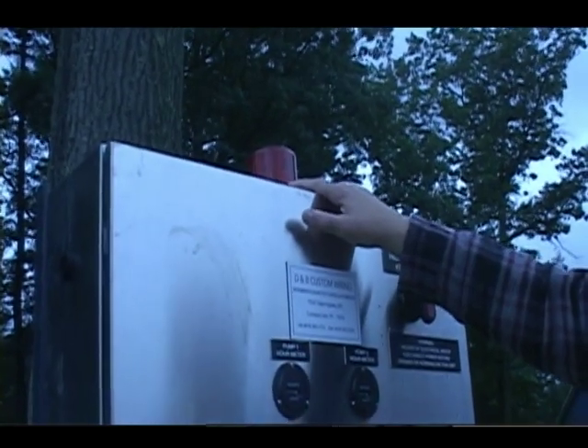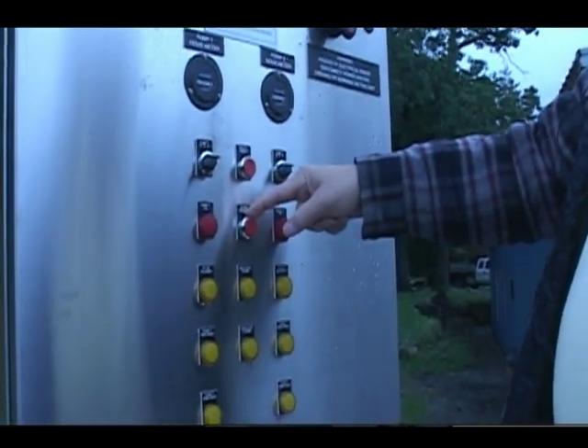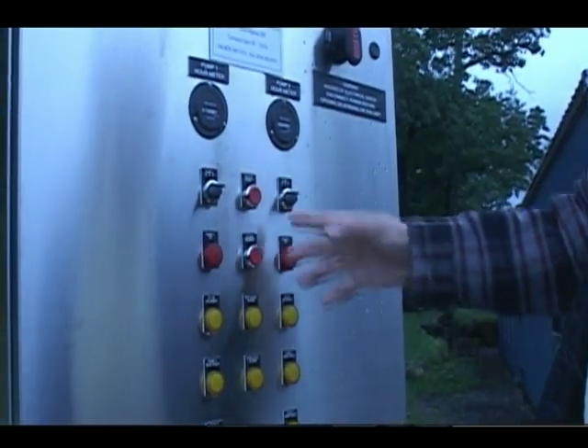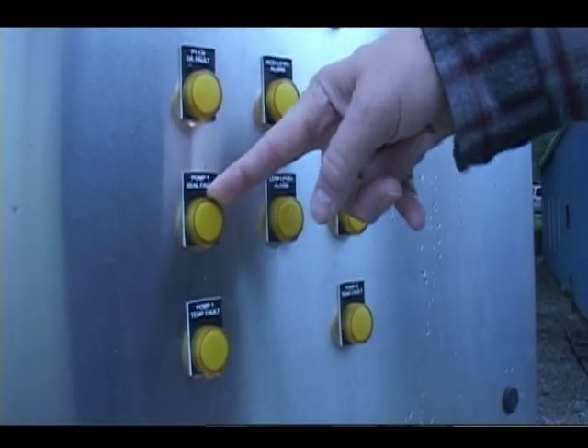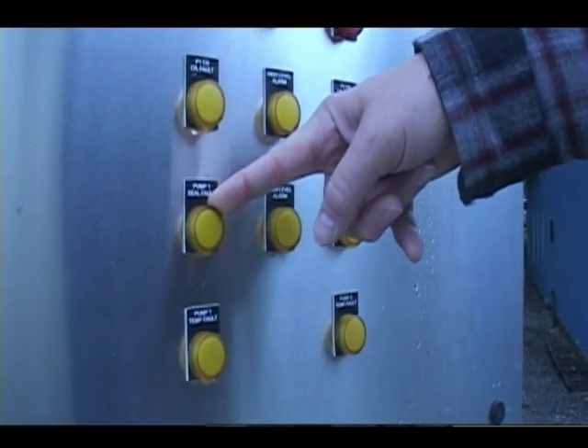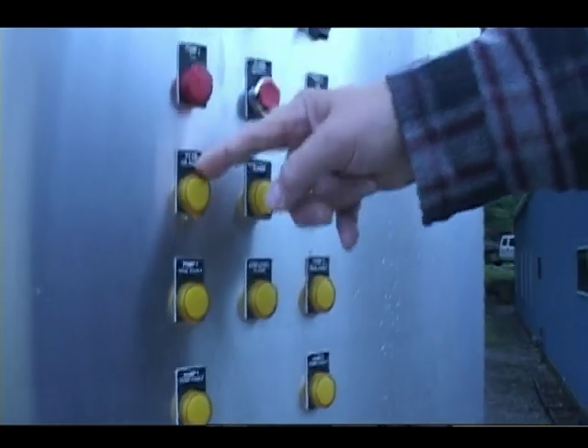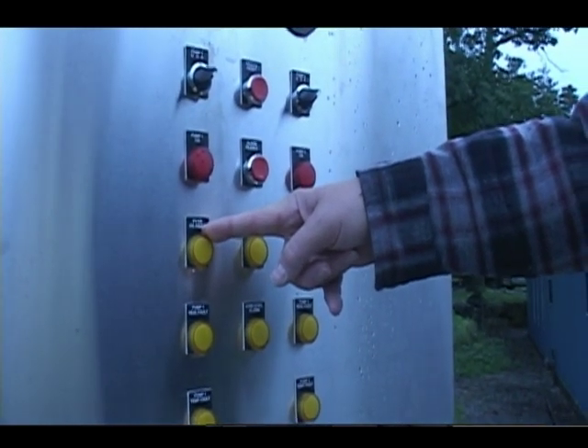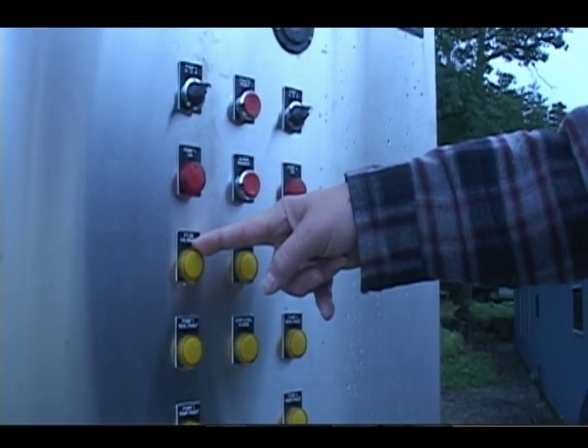If for some reason the pump faults, one of the indicating lights will come on, the high level alarm beacon will come on and sound the horn. To silence the horn, you hit the alarm silence. To reset the faults, you have to look and see what the fault condition was. A temperature sense will reset with the fault reset. The seal fault indicates there's probably an issue with the pump itself, and you need to confer with the pump owner's manual on how to resolve that. The pump circuit breaker overload fault indicates it's a problem with the overload or the circuit breaker inside the panel.